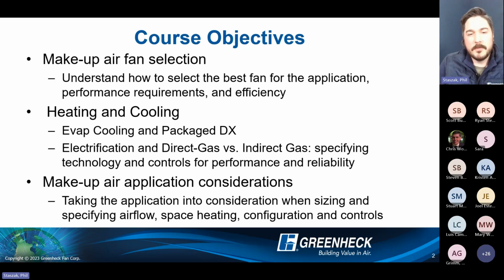But heating matters even in environments cold enough, depending on where you're located in the country, that you risk freezing pipes. There might not even be people in that space, but you may need to discharge, say, 45 to 50 degrees just to prevent anything from freezing. Then there are spaces where you want general tempering to 65 or 70 degrees. So we'll talk about the basic heating functions and spend more time on that.